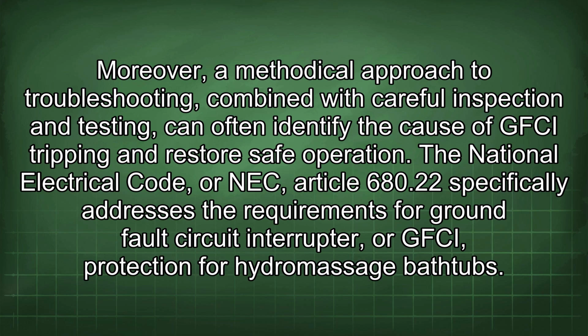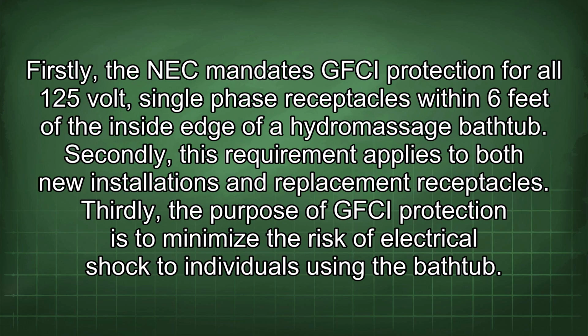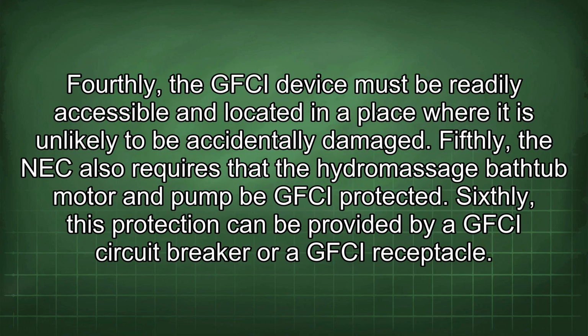interrupter, or GFCI, protection for hydromassage bathtubs. Firstly, the NEC mandates GFCI protection for all 125-volt single-phase receptacles within 6 feet of the inside edge of a hydromassage bathtub. Secondly, this requirement applies to both new installations and replacement receptacles. Thirdly, the purpose of GFCI protection is to minimize the risk of electrical shock to individuals using the bathtub. Fourthly, the GFCI device must be readily accessible and located in a place where it is unlikely to be accidentally damaged. Fifthly, the NEC also requires that the hydromassage bathtub motor and pump be GFCI protected.